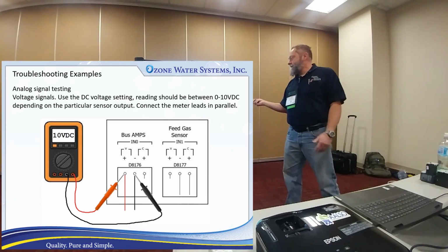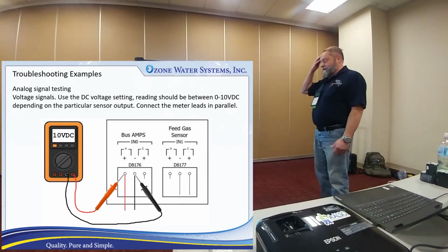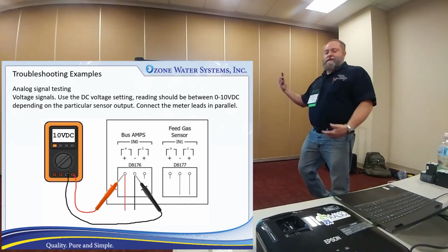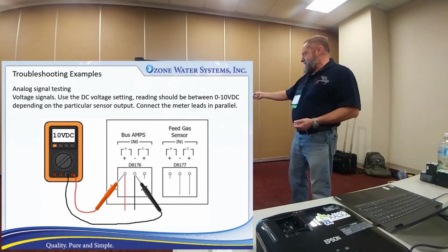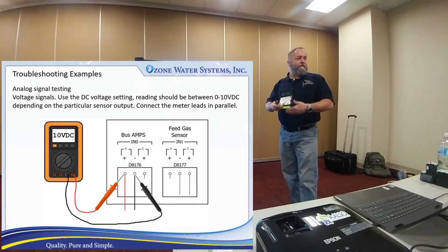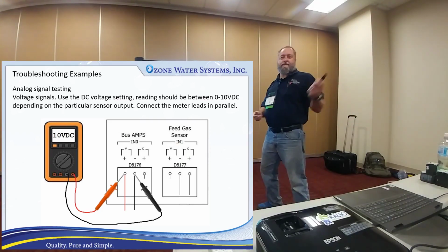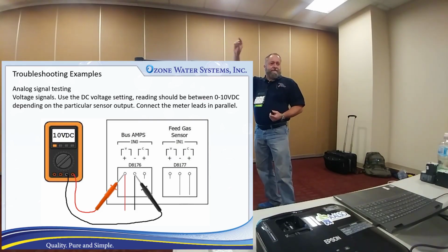You can do it while it's running. You're just going to see a voltage on there, and you can tell what's going on if you know what voltage you're expecting. That particular one is the bus amps coming back from the inverter to tell us how much ozone we're making. So if you've seen our generator upstairs, there's those 2 red bar graphs on the screen.